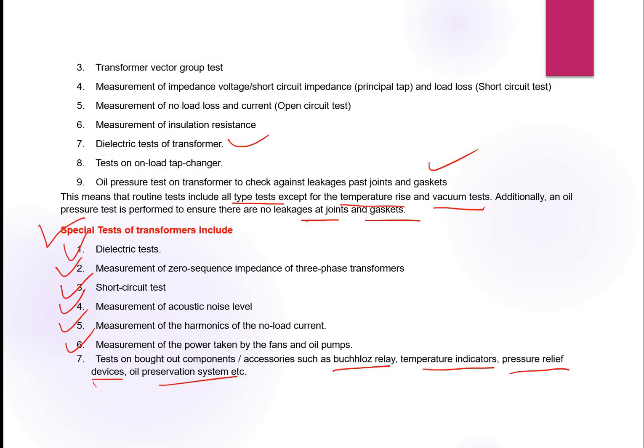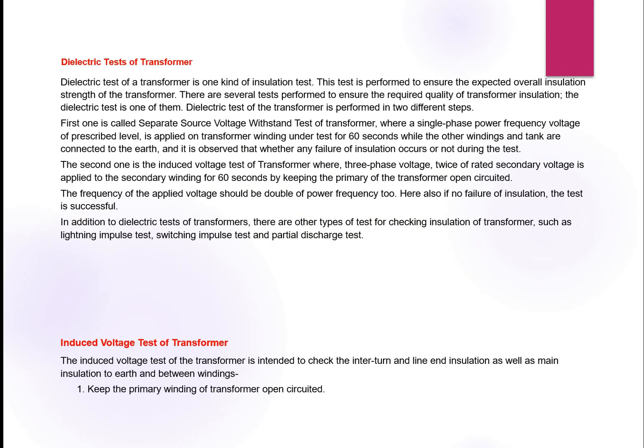A special test is a special test for measuring the dielectric losses, short circuit, acoustic noise level, harmonics. Okay, and dielectric test of transformer. Dielectric test of transformer is one kind of insulation test. This test is performed to ensure the expected overall insulation strength of the transformer, and there are several tests performed to ensure the required quality of transformer insulation. The dielectric test is one of them, and dielectric test of transformer is performed in different steps.